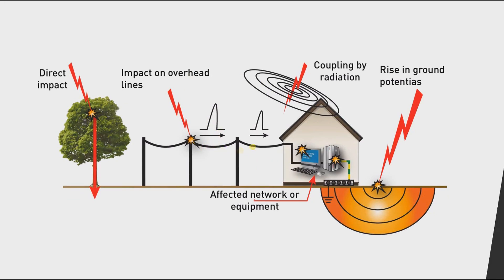A lightning strike can hit a transmission line, leading to overvoltage in overhead lines connected to our equipment. Our equipment is also earthed to the ground, which is normally zero. But if the lightning hits the ground, it raises the ground potential, causing overvoltage on connected equipment. Additionally, both the line and ground strikes produce electromagnetic fields that can induce voltage in our cables through electromagnetic radiation coupling.